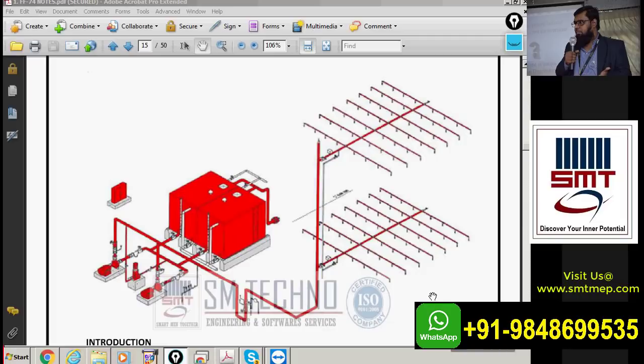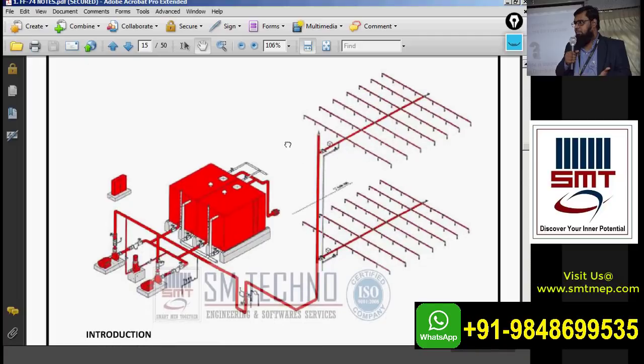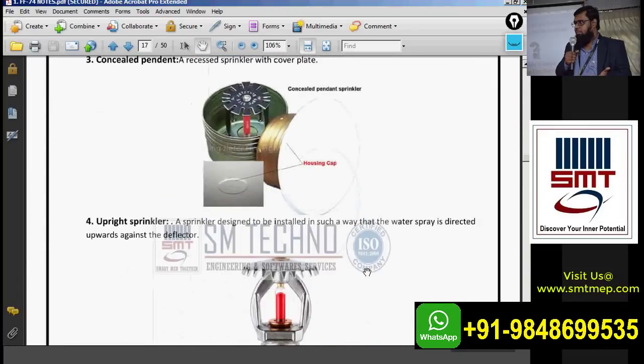If water cannot reach within 60 seconds, a separate riser is added from the same header. Regarding pipe sizing for sprinkler systems, NFPA provides ready-made tables based on light hazard, ordinary hazard, etc. Unlike chilled water pipe sizing, sprinkler pipe sizing is based on probability, following NFPA standards. Generally the cross main and riser take a 4-inch pipe for a standalone sprinkler system, and sizes change if combined with hose reel or Class I/II systems.